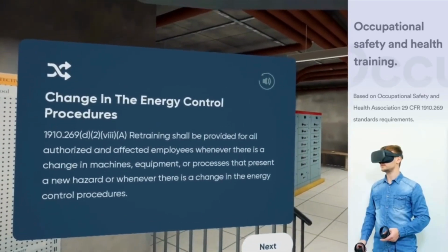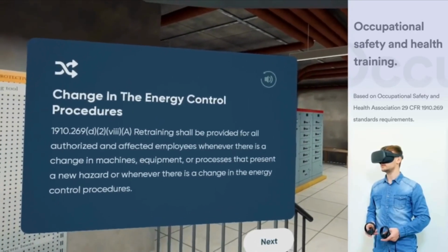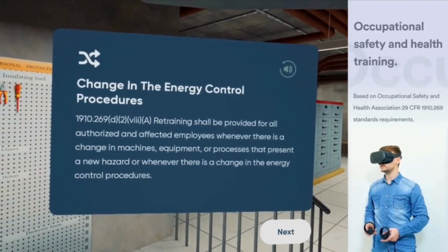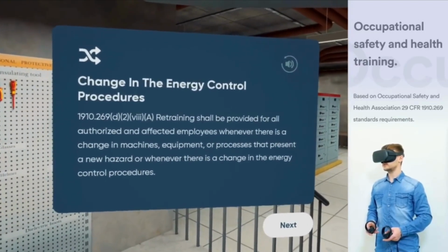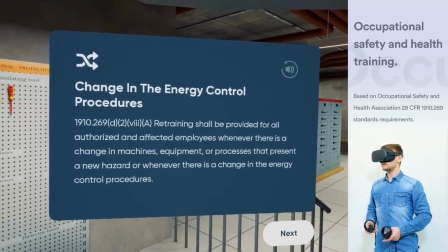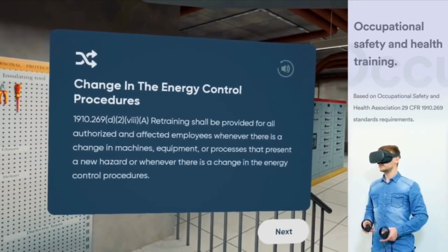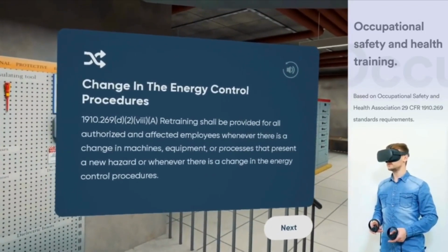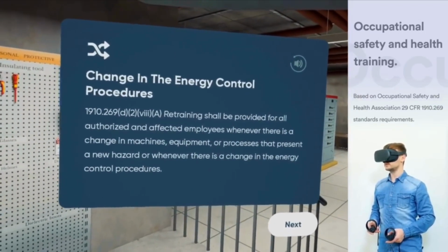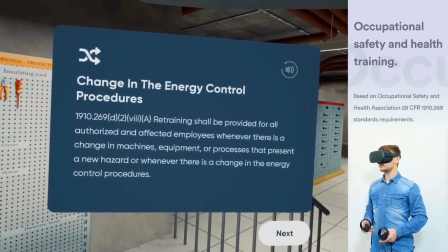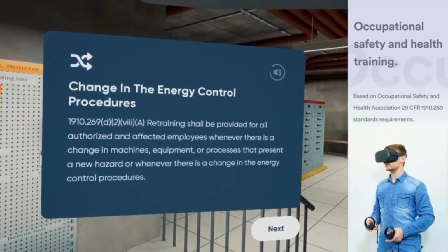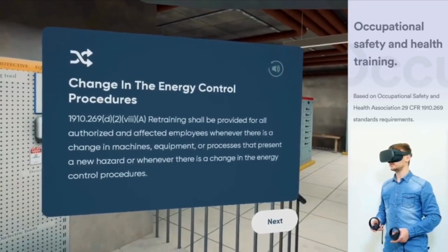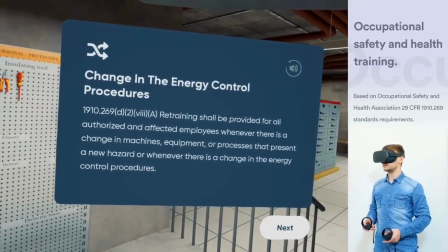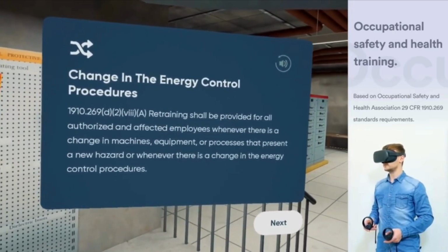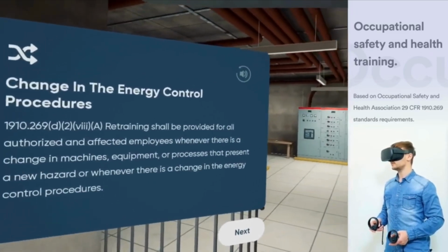Change in the energy control procedures. At some point, the tagged-out circuit breaker had been cross-wired with the other breaker, and thus the panel was not de-energized in fact. According to the OSHA standards, retraining shall be provided for all authorized and affected employees whenever there is a change in their job assignments, machines, equipment, or processes that present a new hazard, or any time there is a change in the energy control procedures.